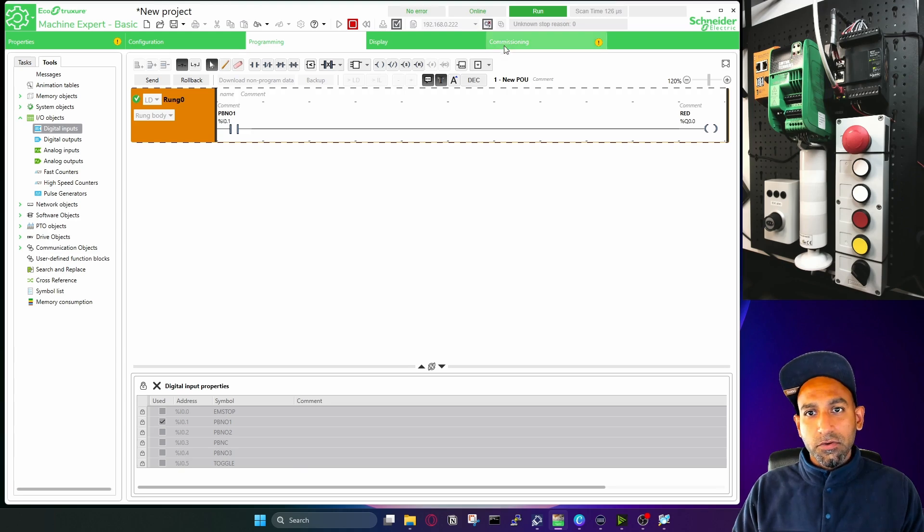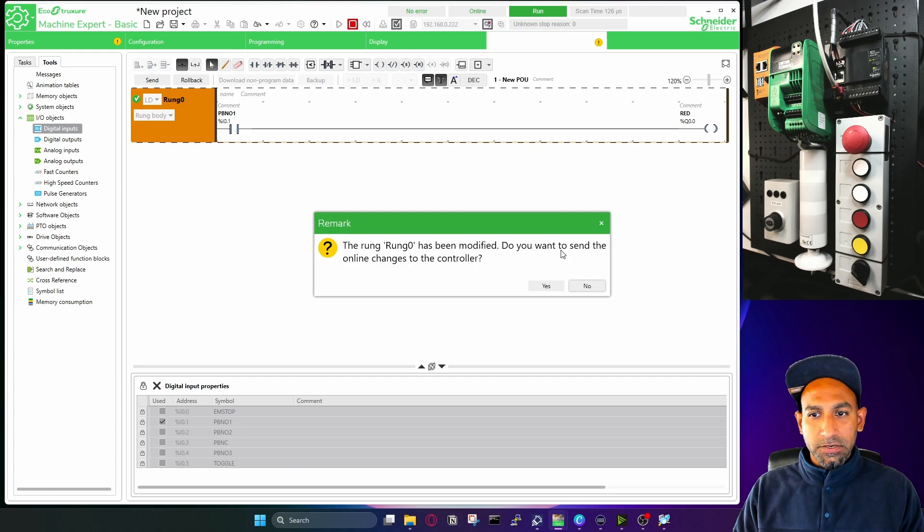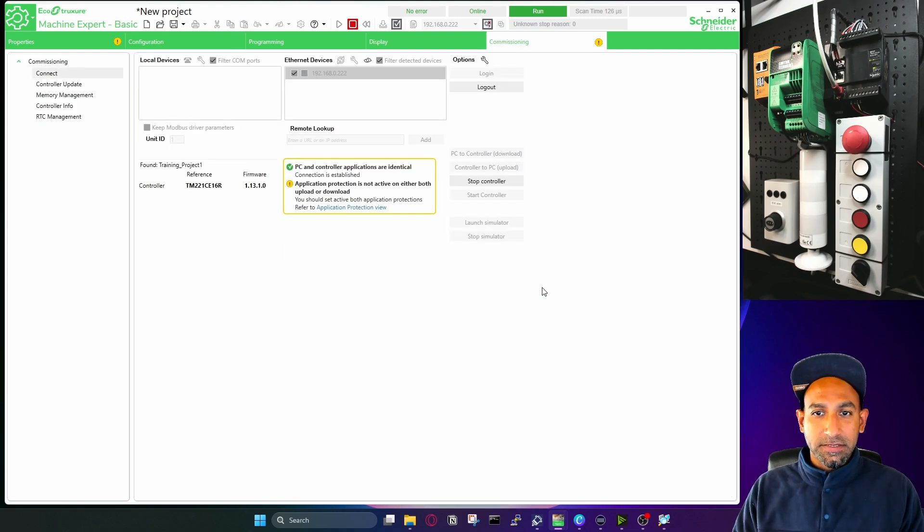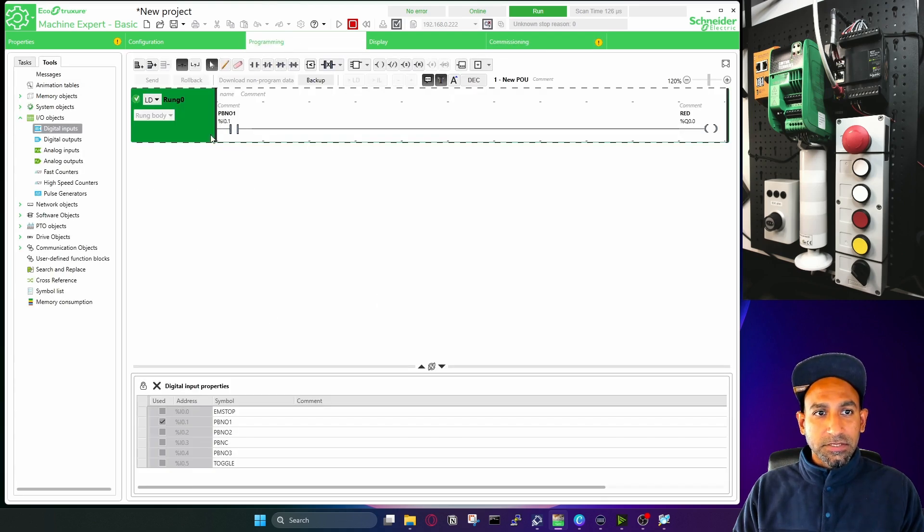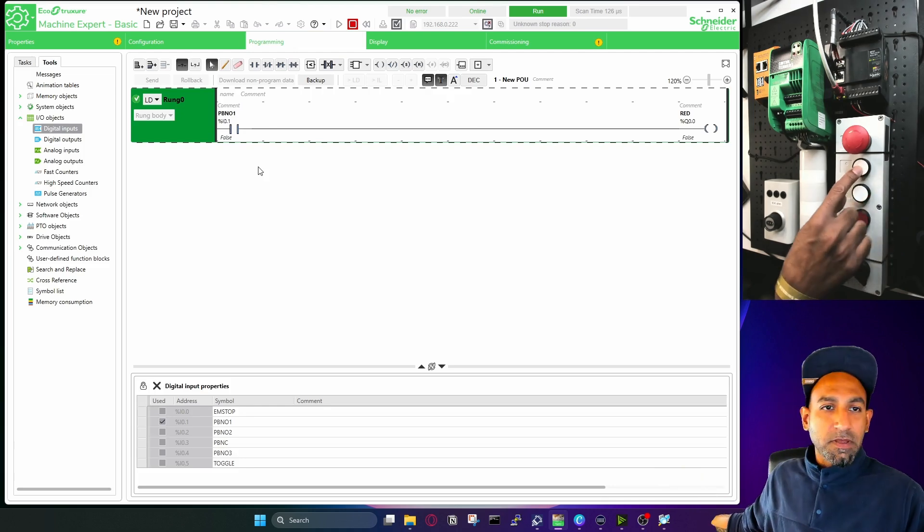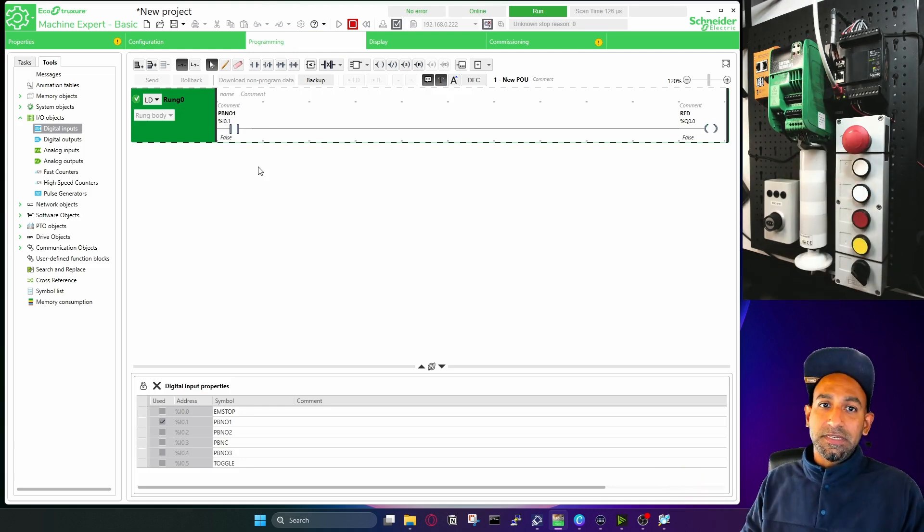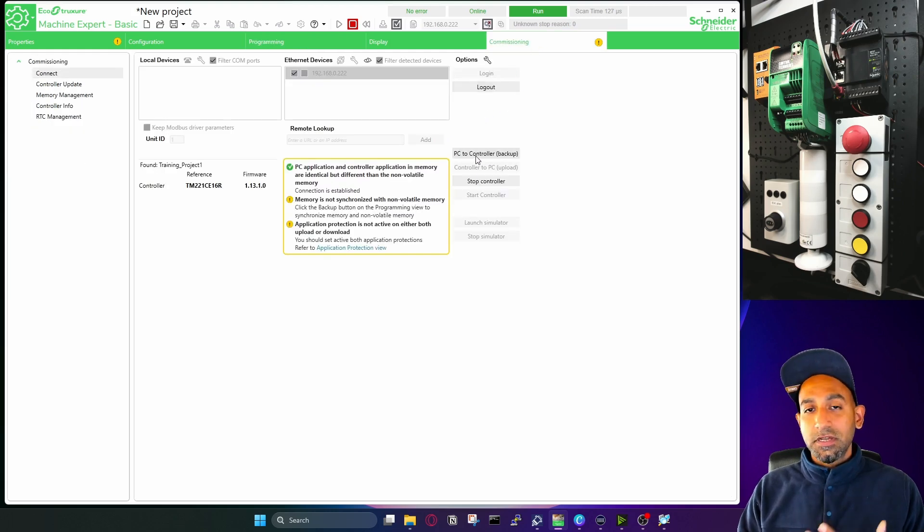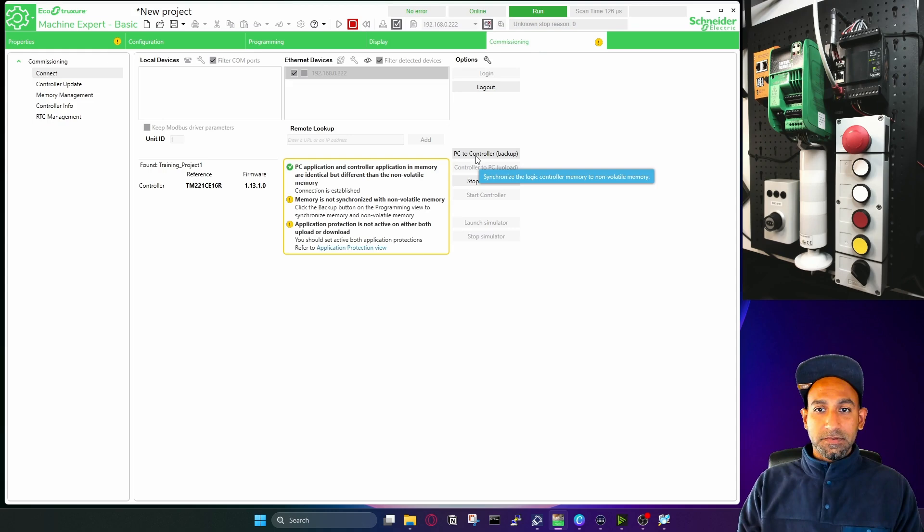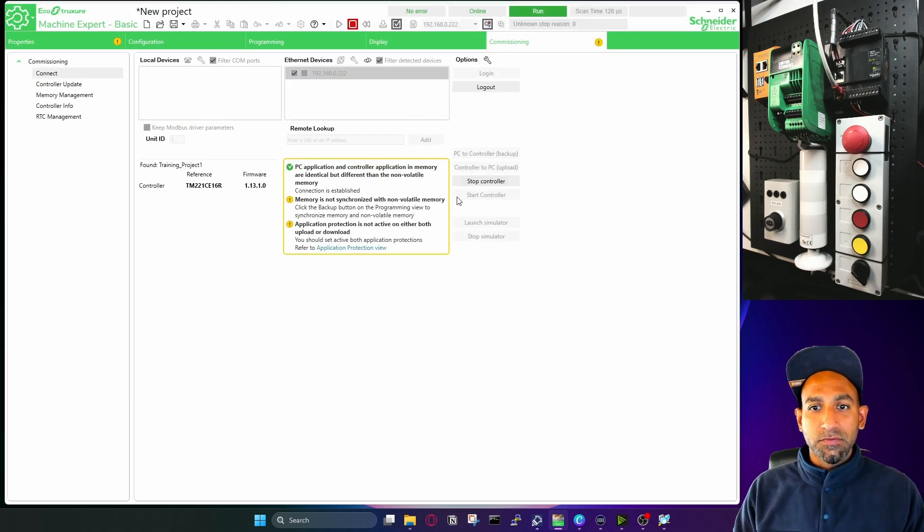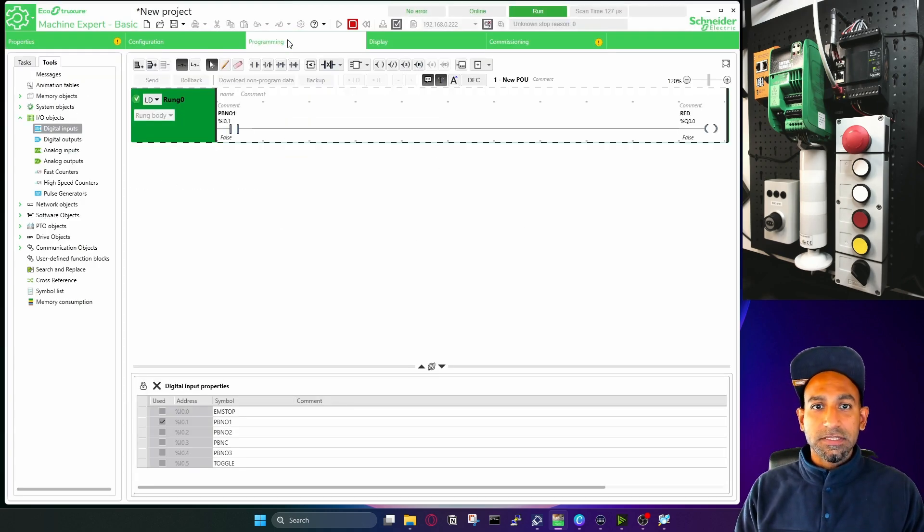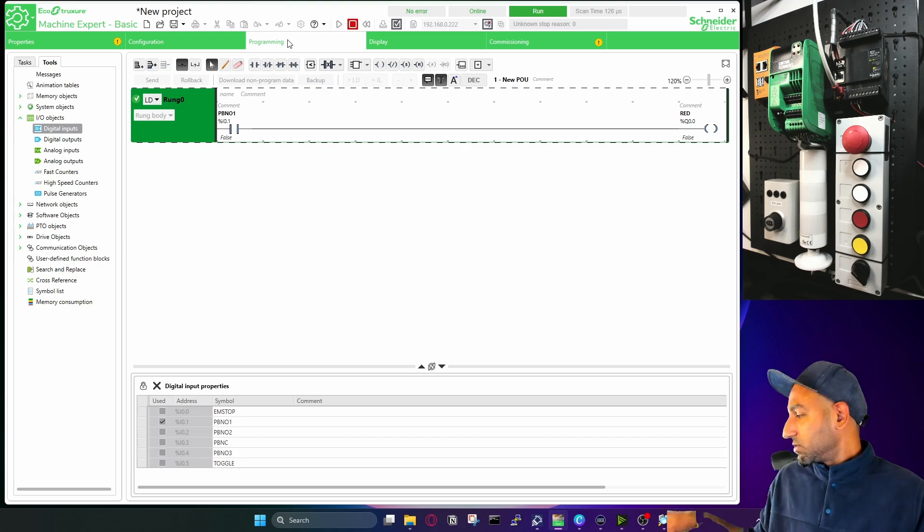So in this case, if I now go to commission, I will have a pop up, the rung has been modified. Do you want to send the online changes to the controller, I will say yes, send these changes to controller. Now, the changes has been sent. So if I now come here, 0.1 is again my first input, it will actuate my output, changes has been done. But we haven't made the backup yet. So we have to send to the controller and tell them this is the final backup, click on that. And then it will write to the controller. Now, it's the final backup, this is what you have to do in the end as well. So there you go.